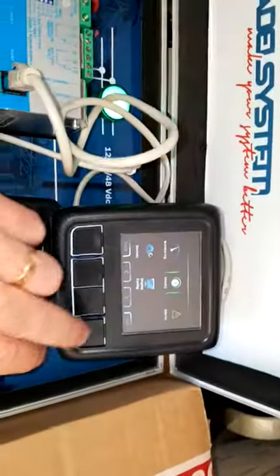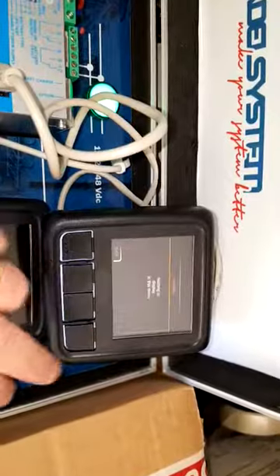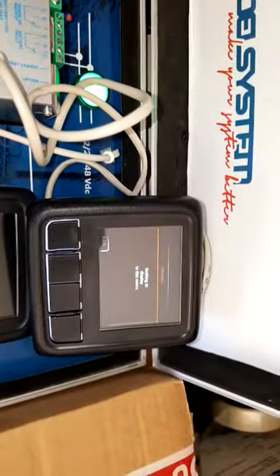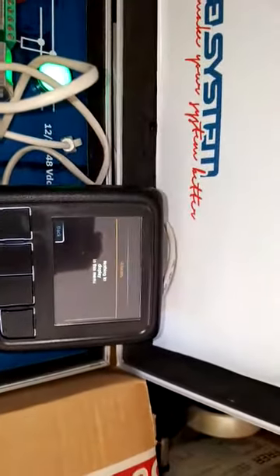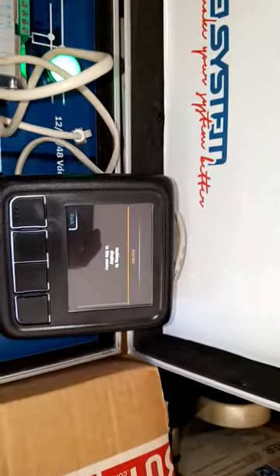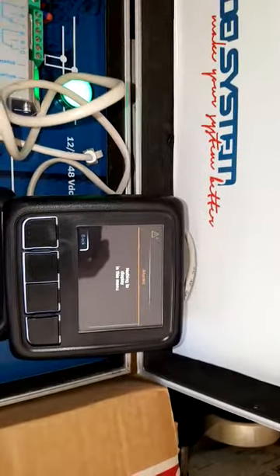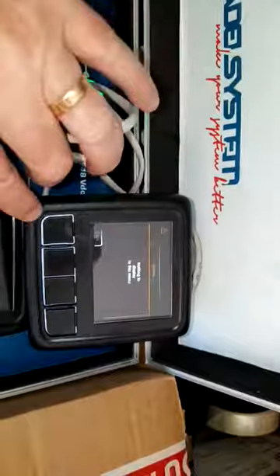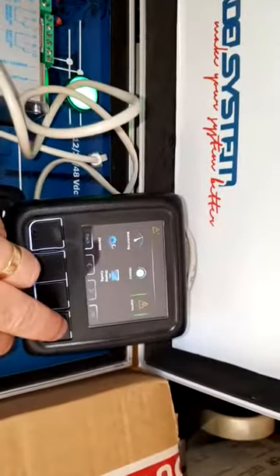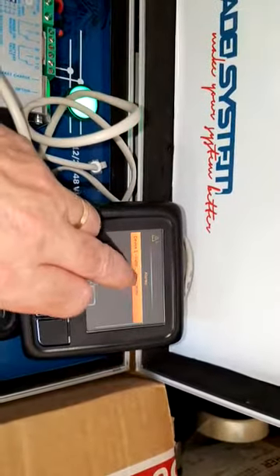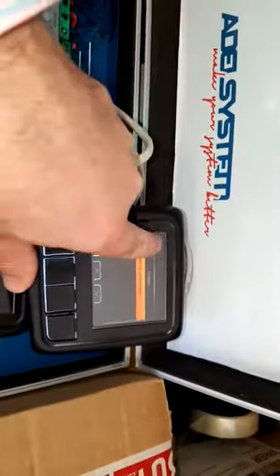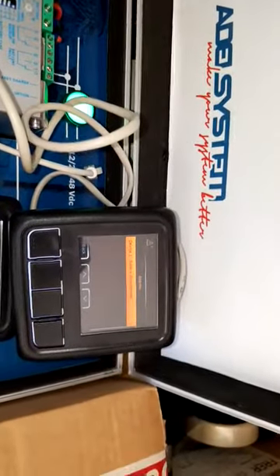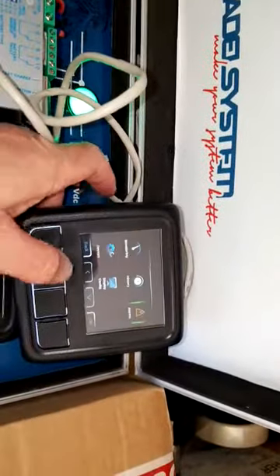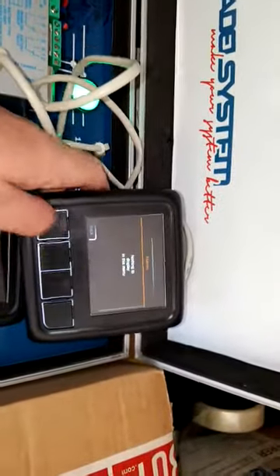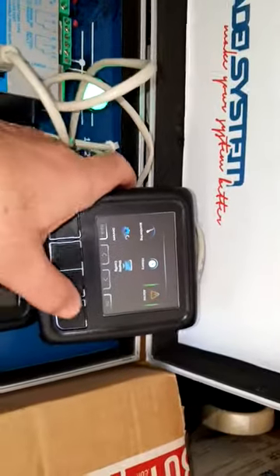So that's that device. And then on alarms, this particular unit should have nothing to display in this menu, so there's no alarm, so I'm going to give it an alarm. I'll disconnect the battery, and there we now have an alarm. If we come back and come in again, it should say battery disconnected, and you can see that this alarm comes on there. If I restore the battery, that should go away, and I come back in and go okay, it's gone. So that's your alarms.